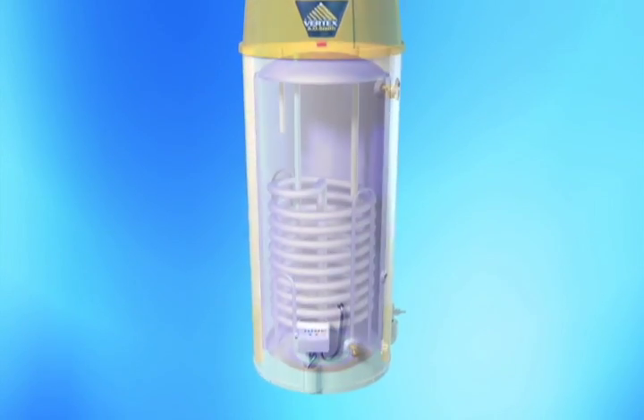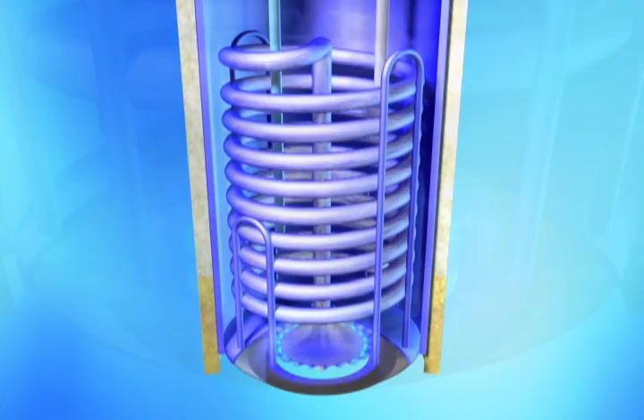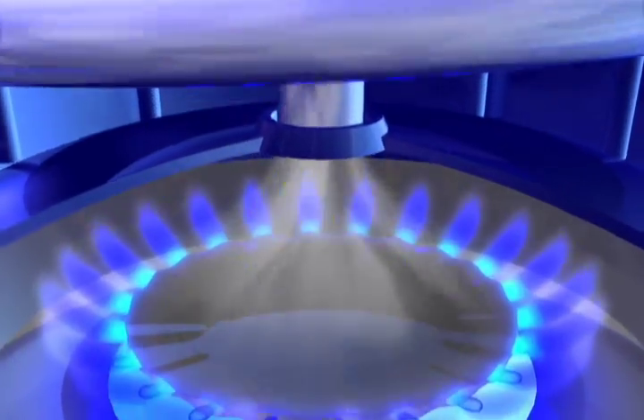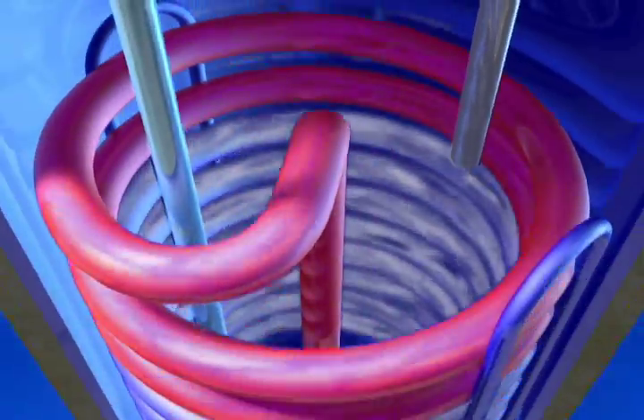With A.O. Smith's Vertex, the vertical flue tube is replaced by a helical coil heat exchanger. Heat transfer still takes place through the tank bottom, but instead of venting straight up and out, hot gases are drawn by the power vent blower up, around, and down through the coil.